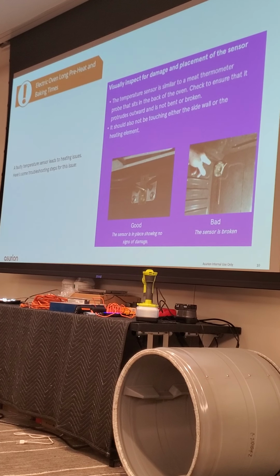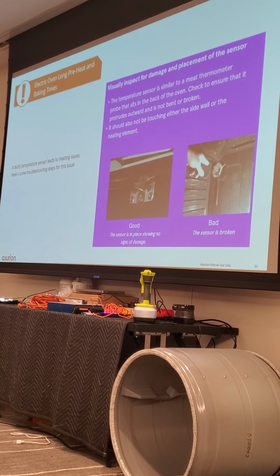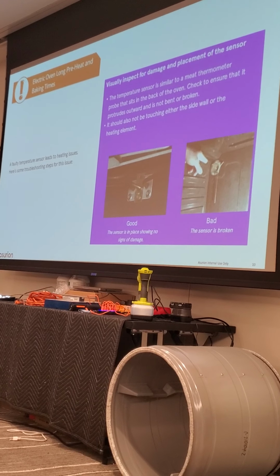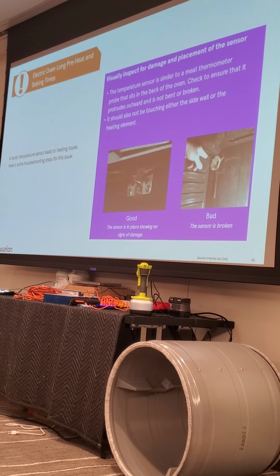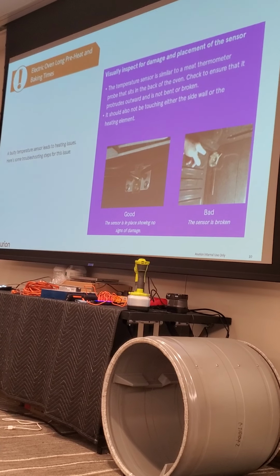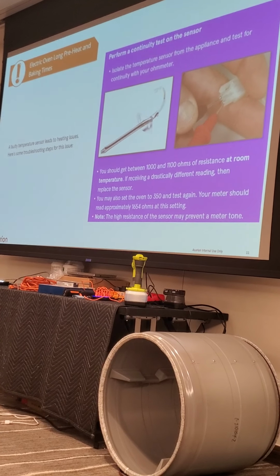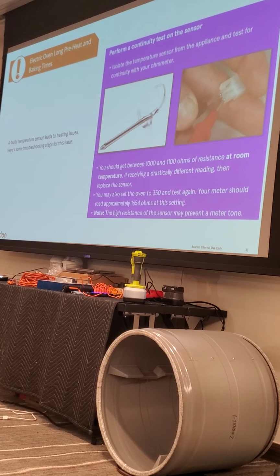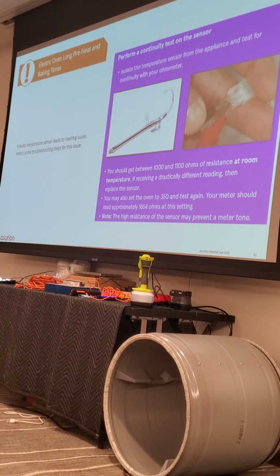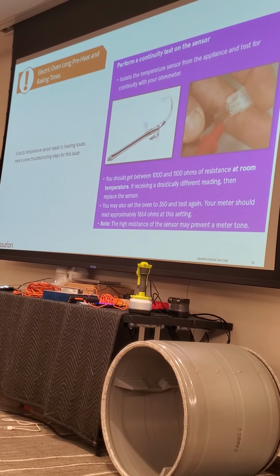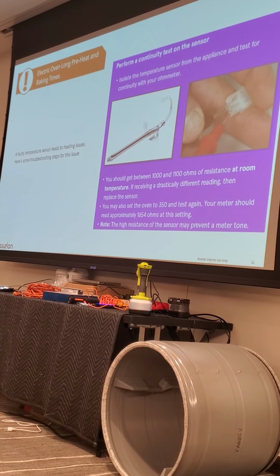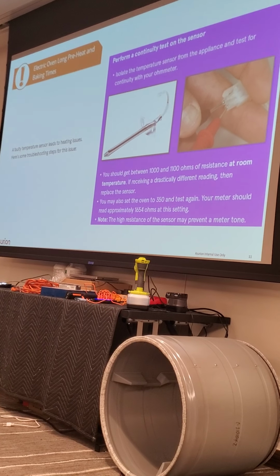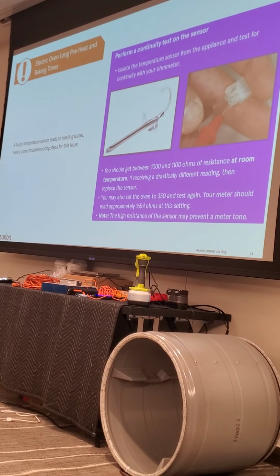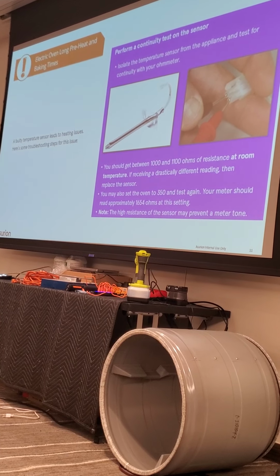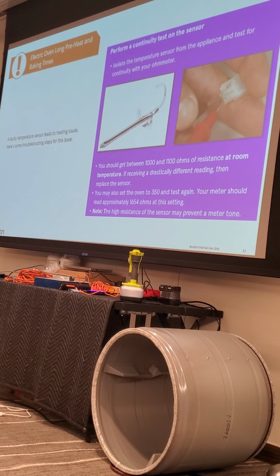Okay, a faulty temperature sensor. We've already gone over the temperature sensor a little bit, so we won't spend too much time on that. I've already told you some of the things that could be going wrong with it, so let's move on. So there's your temperature sensor. Like I said, you can test those outside of the cabinet without having to turn that oven on. Know what the ohms are, know what the chart is. STG always lists the chart. Okay.